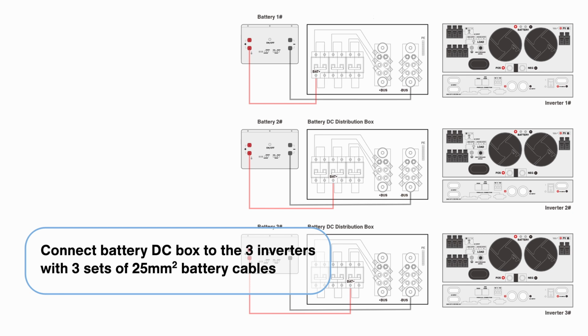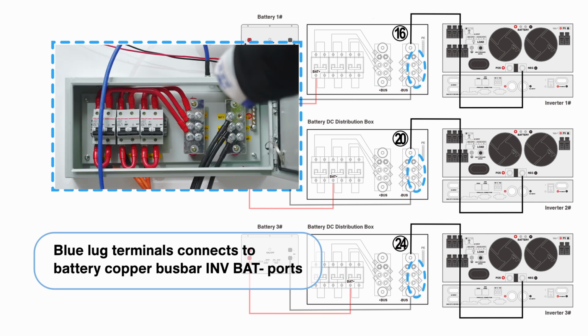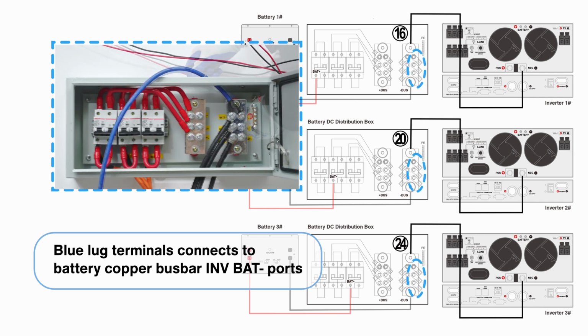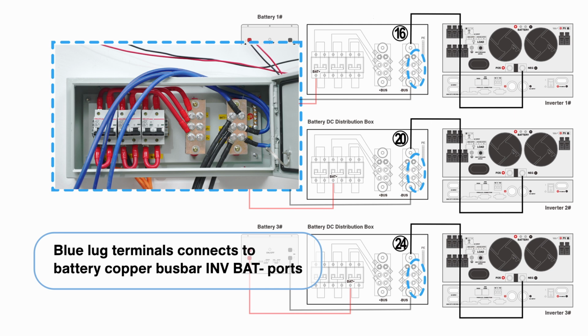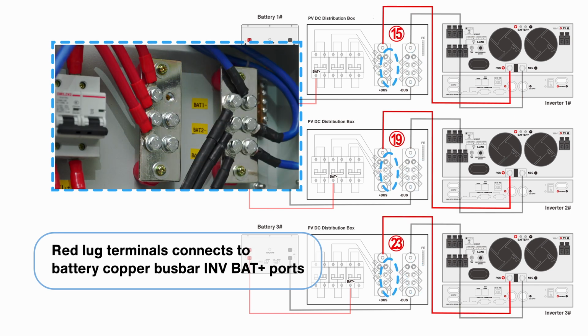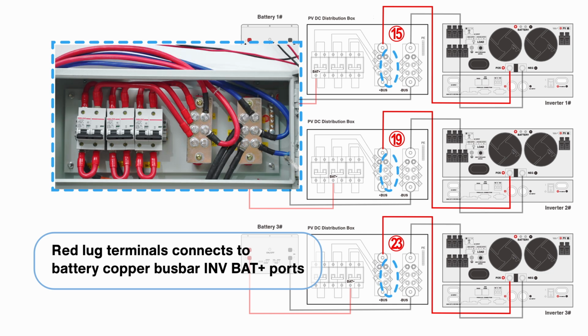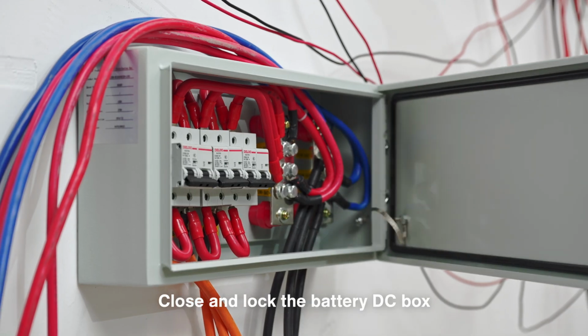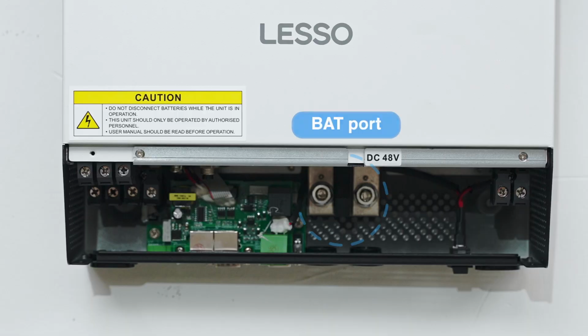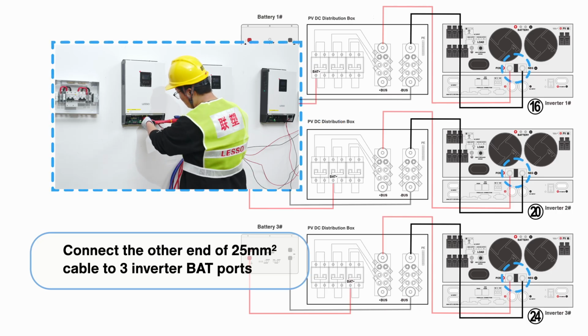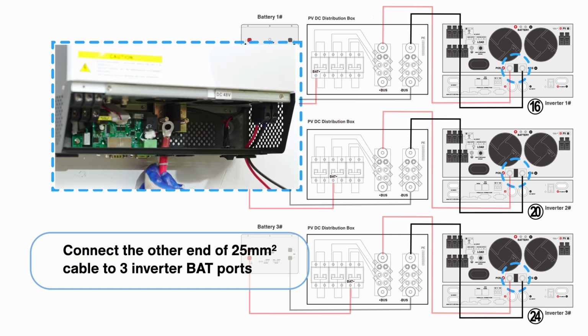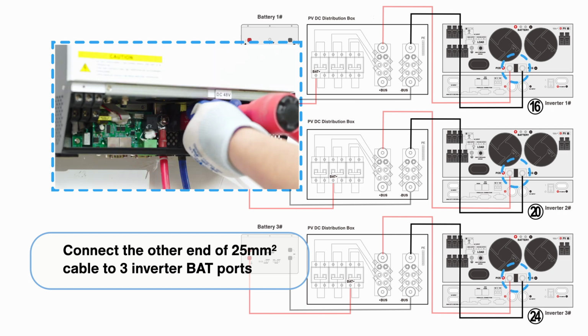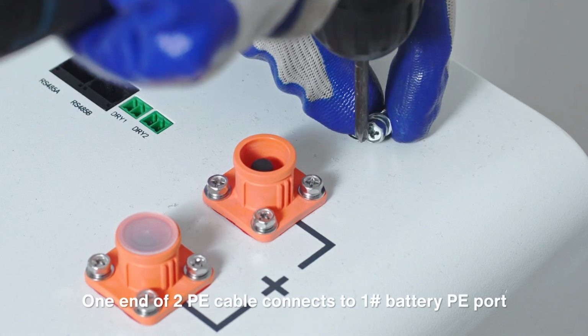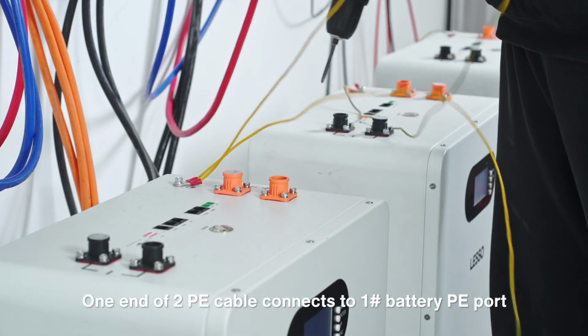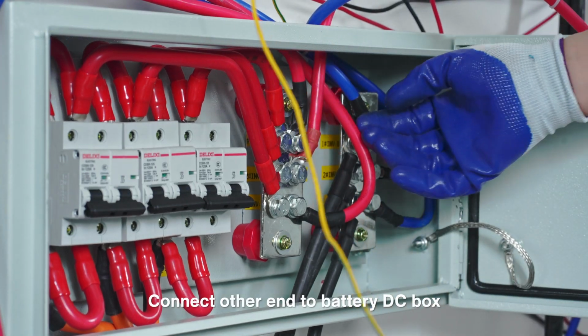Connect battery DC box to the 3 inverters with 3 sets of 25 mm squared battery cables. Blue lug terminals connects to battery copper busbar INV BAT- ports. Red lug terminals connects to battery copper busbar INV BAT plus ports. Close and lock the battery DC box. Connect the other end of 25 mm squared cable to 3 inverter BAT ports. One end of 2 PE cable connects to 1 number battery PE port. Connect other end to battery DC box.